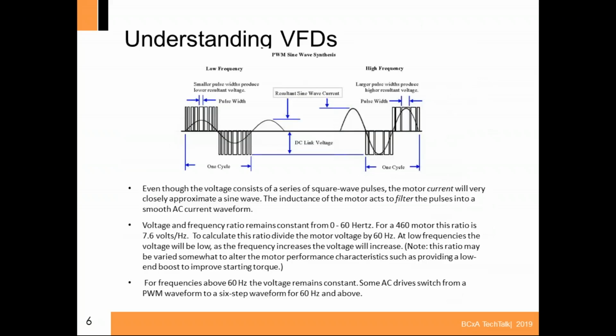I'll talk a little about VFDs because we can't really talk about direct drives until we talk about VFDs. This is something I think I got out of NEMA, so you can see how a pulse width modulation drive works. What it does is it modulates the voltage on and off to create a different wave. So we might have on the line side, for instance, 460 volts, coming from the panel to the VFD.